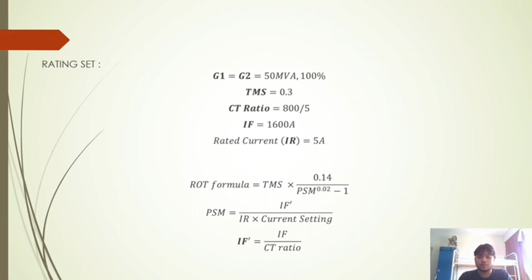For the first one, circuit breakers R1 and R12, the setting current is 100%. First we have to find IF secondary, which is 1600 over the CT ratio, that is 800 over 5, which equals 10. So the PSM will be 10 divided by 5 multiplied by 1. Putting it in the ROT formula, we got 3.01 seconds. For circuit breakers R21 and R23, the IF is equal to 10, the PSM, plug setting multiplier, is equal to 1.6, and the ROT we get is 4.47 seconds.